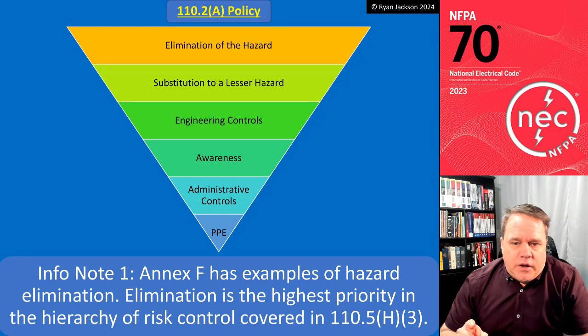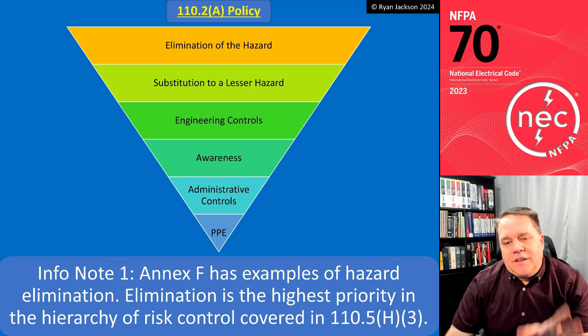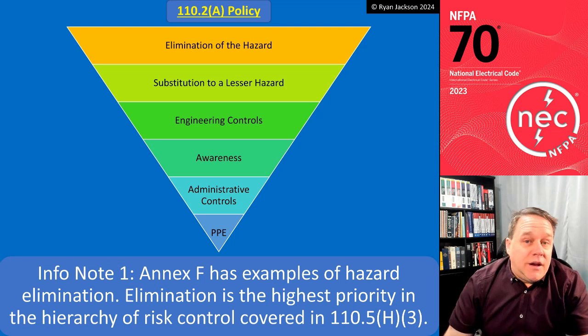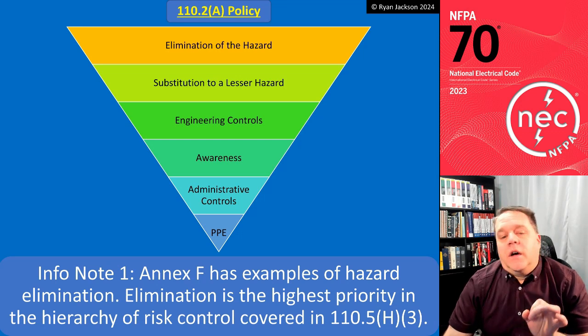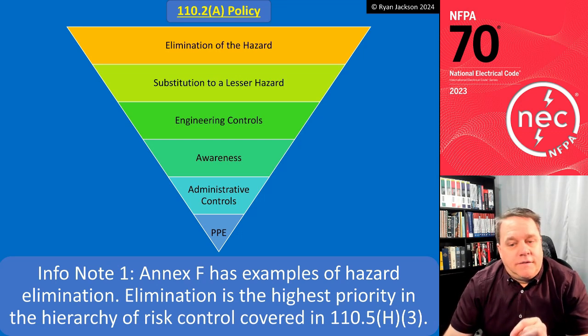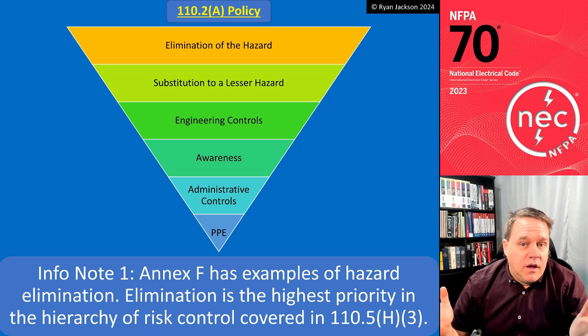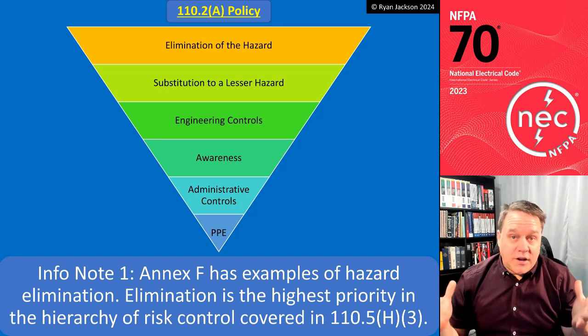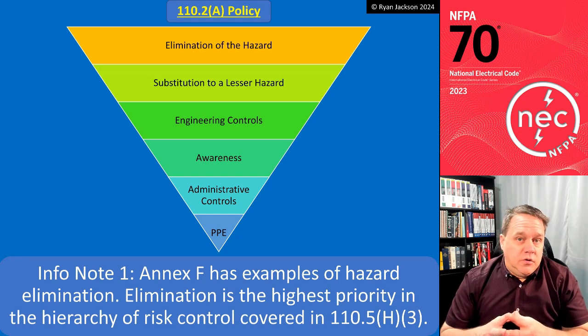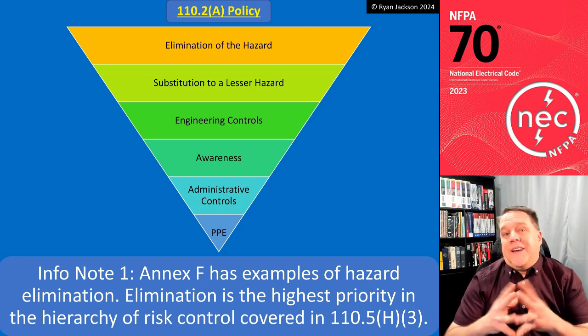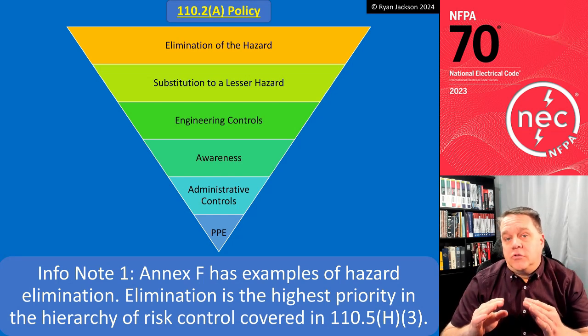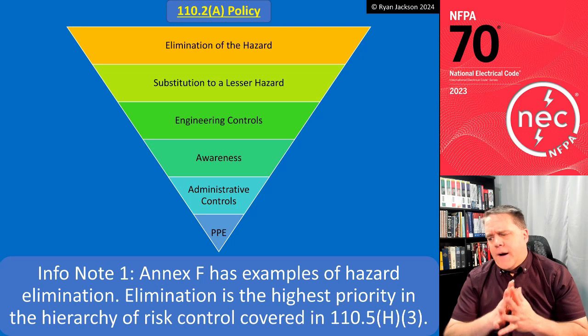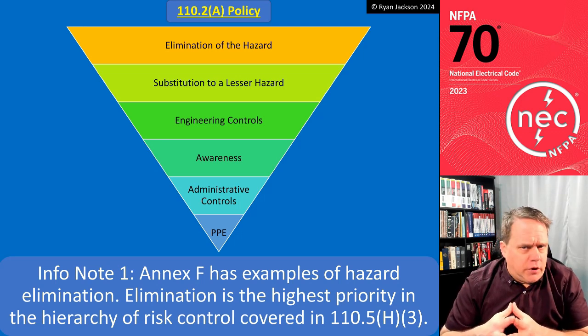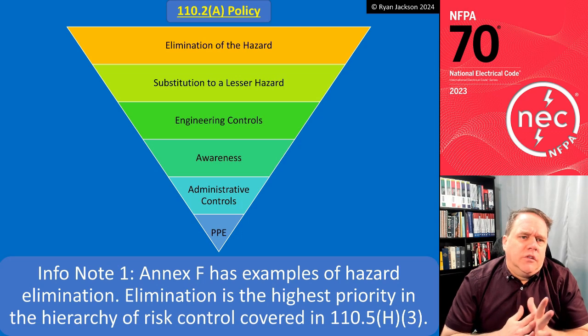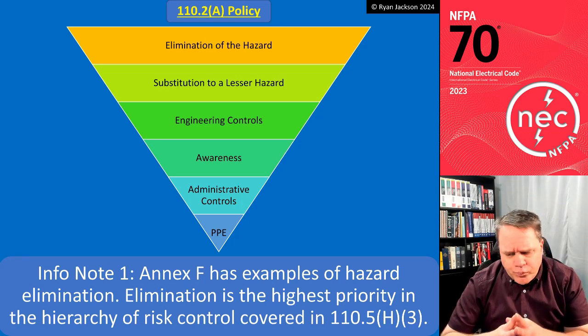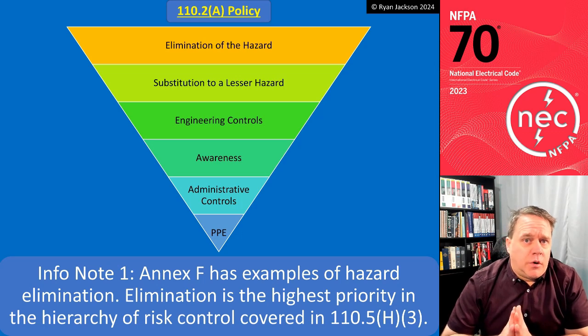There's an informational note here that says Annex F has examples of hazard elimination. Elimination is always the highest priority in the hierarchy of risk control covered in 110.5H3 because it's the most effective. So if I want to not get injured, then obviously the best thing I could do is to eliminate the hazard. Or if I can't eliminate the hazard, maybe I can substitute to a lower hazard, right? A lesser hazard. Maybe I've got to troubleshoot a motor. One of the things that people have a misconception of is whether or not you can work energized. Well, sometimes working energized is part of being an electrician.